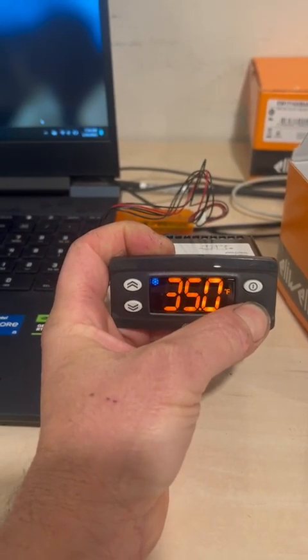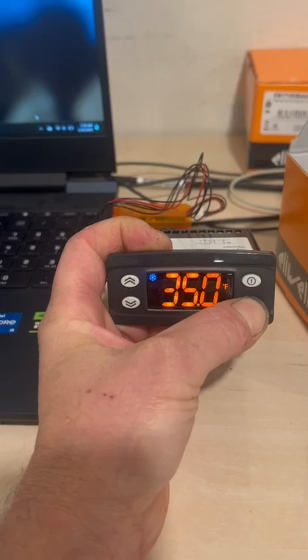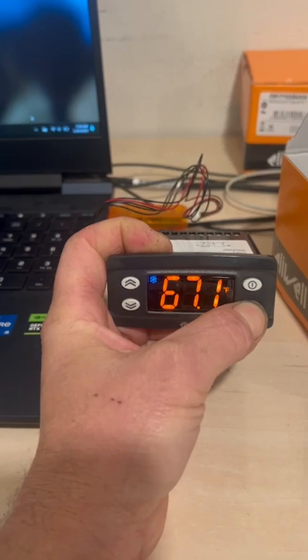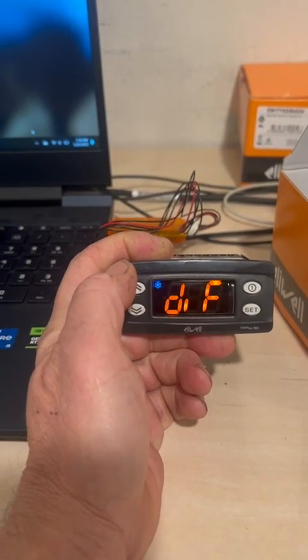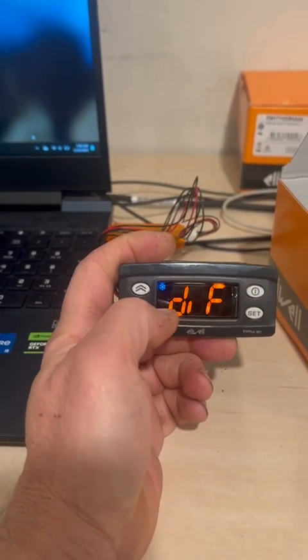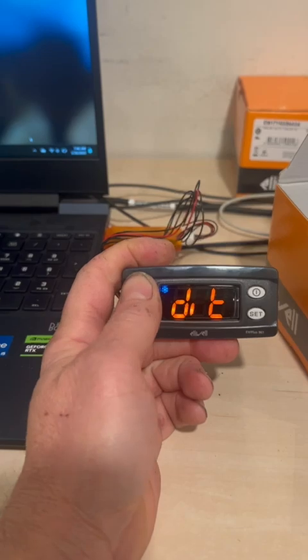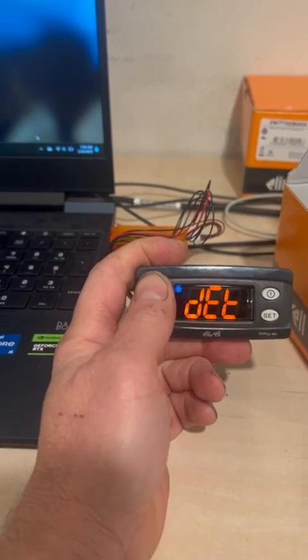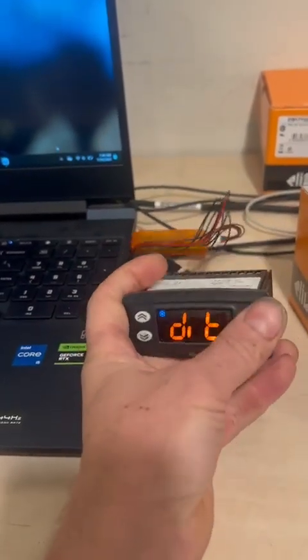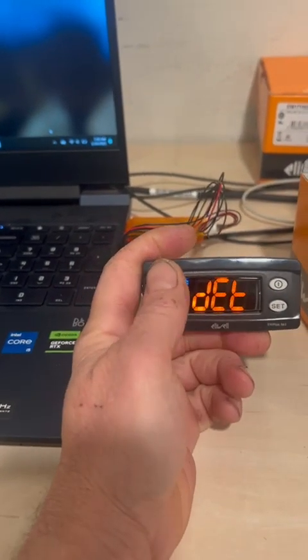Once inside the program, you can change the parameters of the controller. The differential — the difference between start and stop — is five degrees, so if we stop at 35 it's going to start at 40. You also have higher set, lower set, dit, and dEt — the defrost interval, set to every six hours — and defrost endurance, set to 30 minutes.